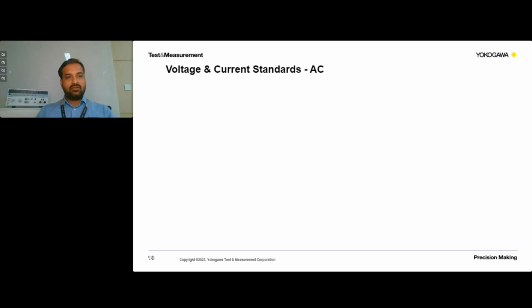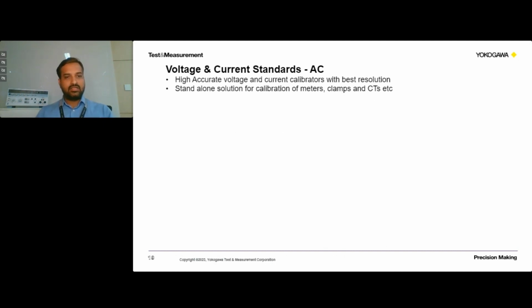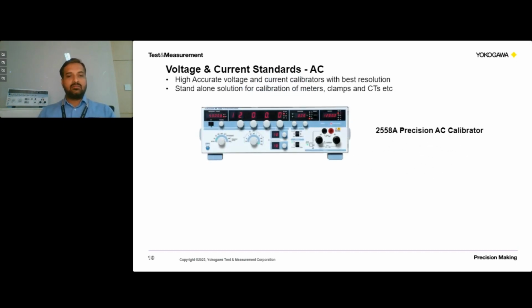We have voltage and current standards for AC parameters. We have highly accurate voltage and current calibrators with the best resolution available in the market, and these are standalone solutions for calibration of panel meters, clamp-on meters, CTs, those kind of products. This is how the product looks, and the model number is 2558. It is a precision AC calibrator.